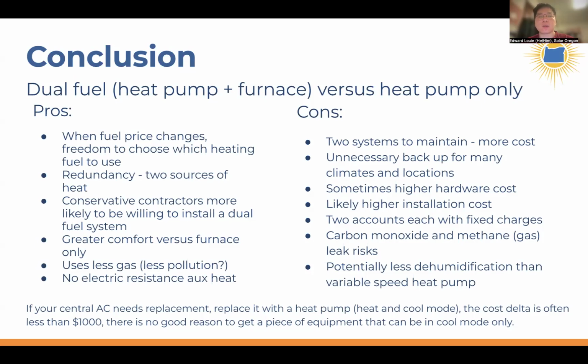Some cons of a dual fuel system: you have two systems to maintain. That's more cost, and it's unnecessary backup for many climates. Sometimes it's a higher hardware cost, but as I said, the higher hardware cost is usually a wash. Certainly there is likely to be a higher install cost because of the need to pipe the natural gas, vent it, and test all the leaks and safeties associated with having gas. And then there's a risk of carbon monoxide and gas leaks when you have gas in your house.